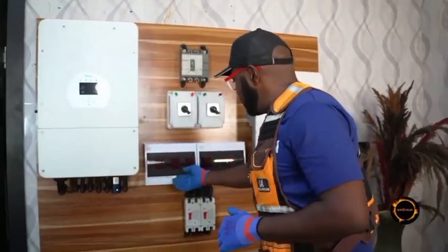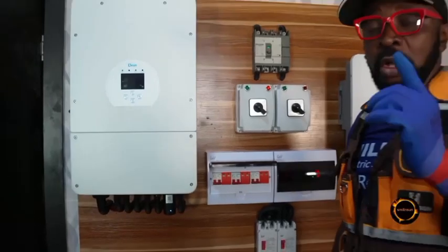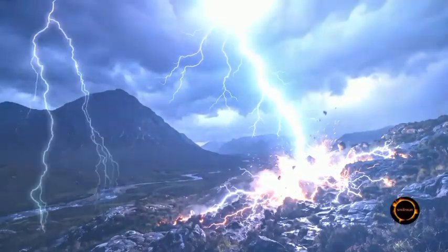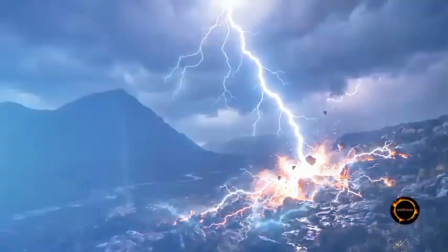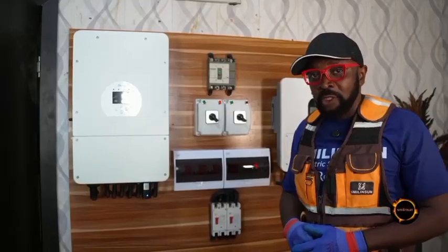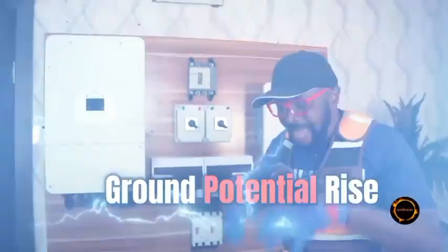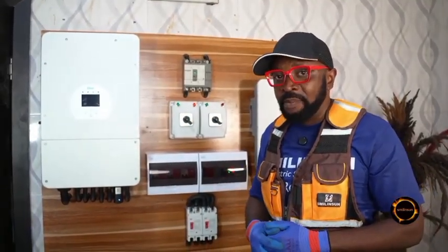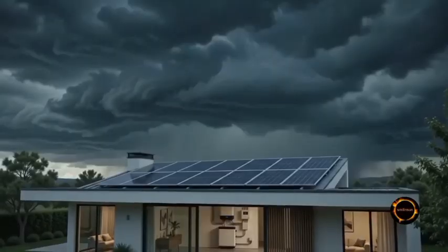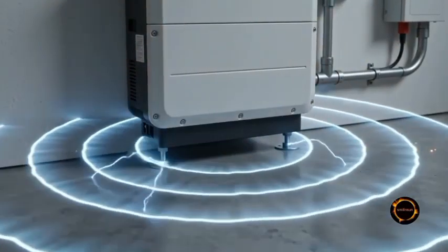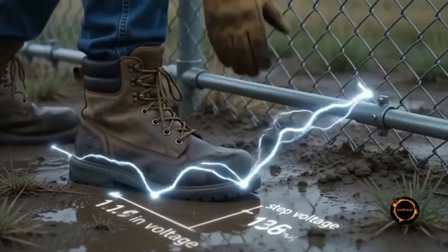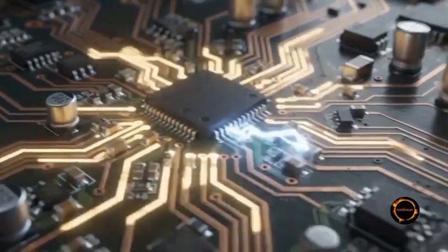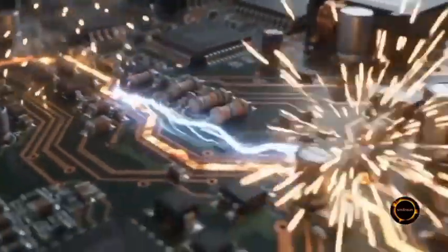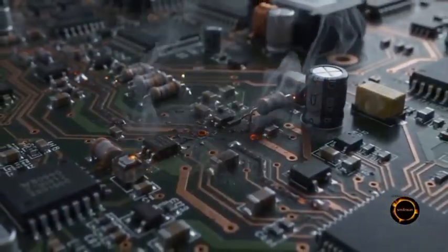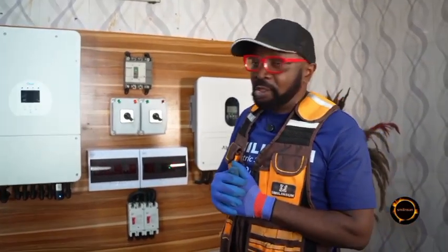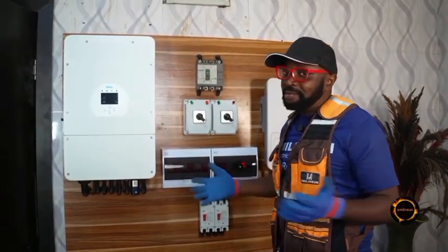Now the major reason why turning off your circuit breakers will not help you is the fact that when lightning strikes, it injects a lot of electrical energy into the ground. And when it does that, it causes what you call ground potential rise. When that lot of energy and current overwhelms the ground, it rises and moves in a reverse mode, headed to where? Of course, to your appliances and your inverter. And when it comes, because the voltage is so much, it's going to jump over your closed circuit. So it doesn't matter if your circuit is closed or open, it's going to jump it because the potential and voltage are so much. So merely closing down your circuit breakers is not going to help you.